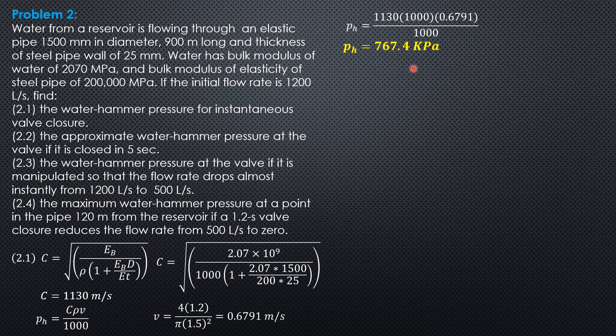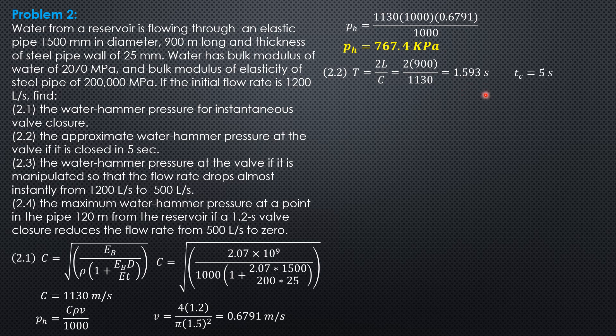For Part B, the approximate water hammer pressure at the valve if closed in 5 seconds. The actual time of closure is 5 seconds. The time for the pressure wave to travel a round trip is 2L/C = 2 × 900 / 1,130 = 1.593 seconds. Since actual closure time of 5 seconds is greater than 1.593 seconds, this is a slow closure. By proportion: pH' / 1.593 = 767.4 / 5. Therefore pH' = 244.5 kilopascals.